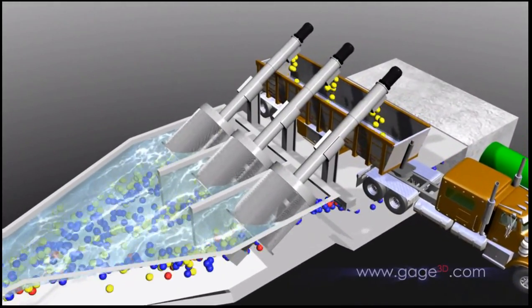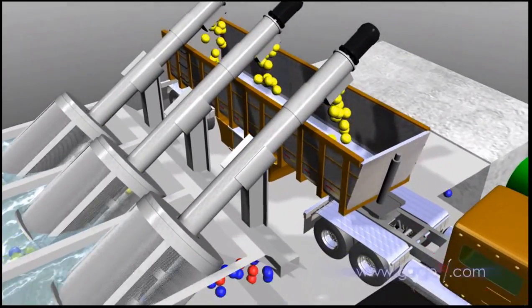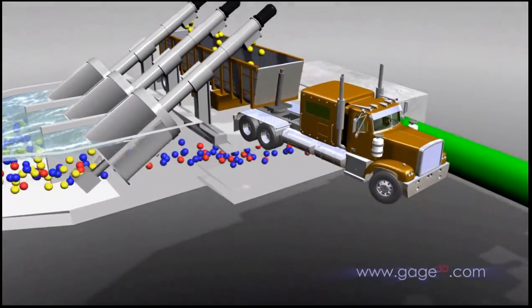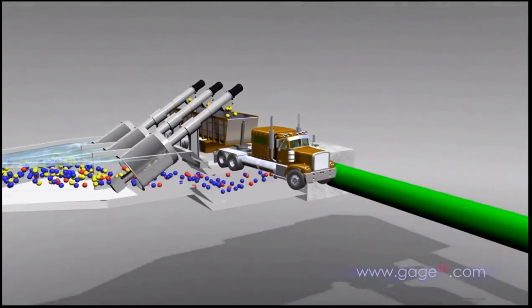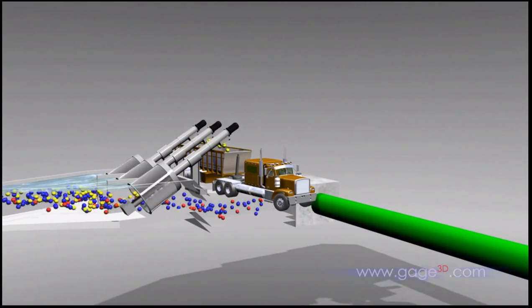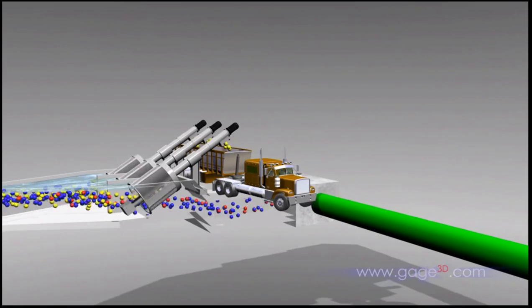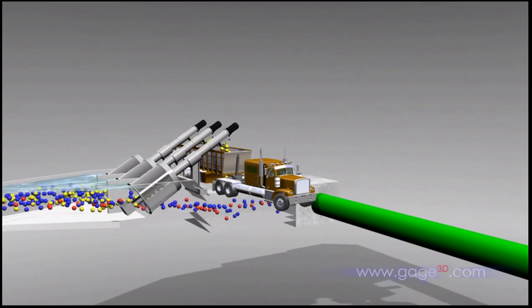The main goal of primary treatment is to separate water from solids, known as organic matter. This differs from the headworks, which is designed to remove inorganic waste like trash and grit. Like the headworks, primary treatment relies on physical separation methods, such as screening and sedimentation, which causes sediments to settle out by gravity.